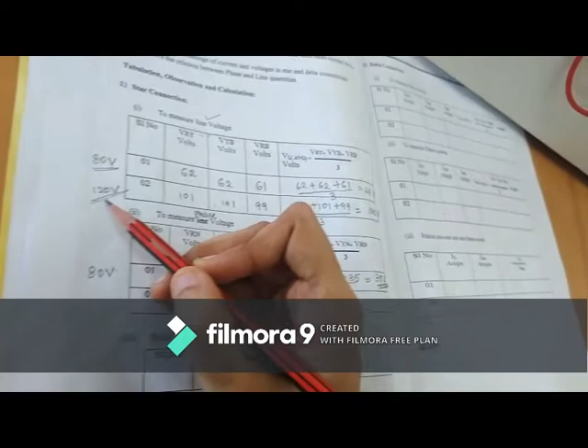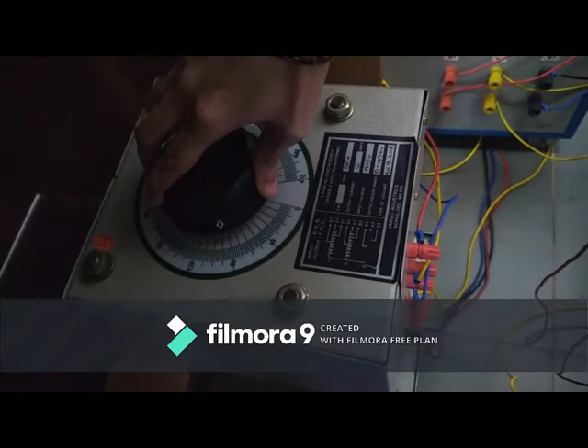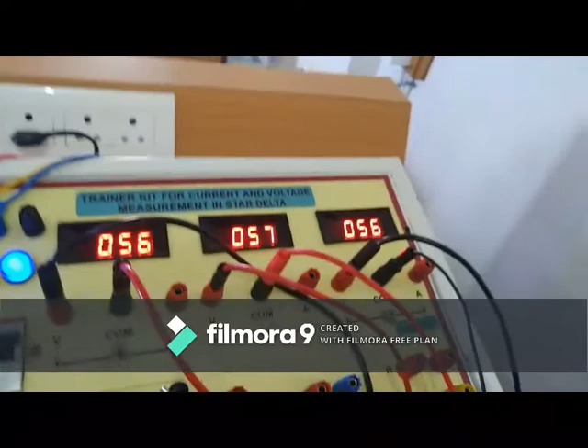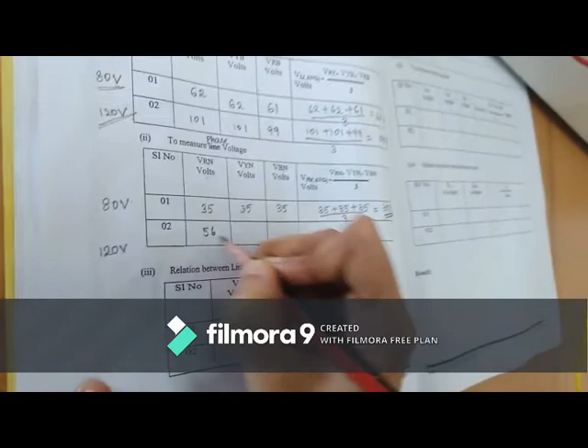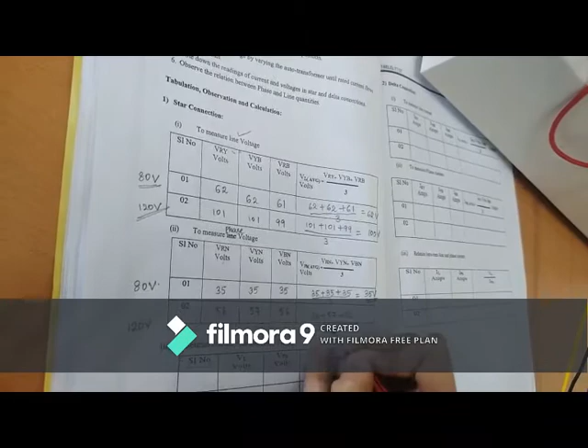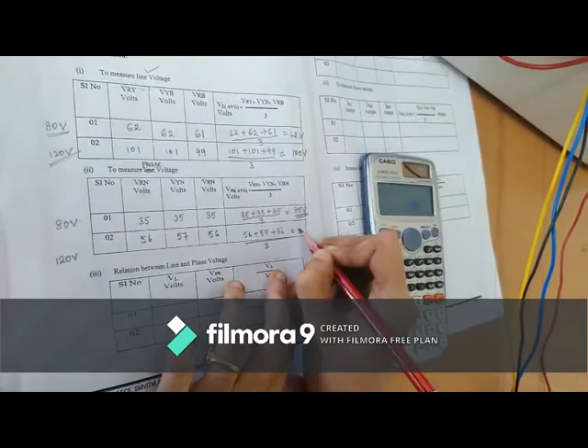Again I will change the applied voltage, since in my first case of measuring line voltage I assumed the second value as 120 volts. Similarly I am going to apply 120 volts through the auto transformer for the second case. The voltmeter readings are 56, 57 and 56 - that is 56 for VRN, 57 for VYN, and again 56 for VBN. The average value is 56 plus 57 plus 56 volts divided by 3, which approaches a value of 56 volts.